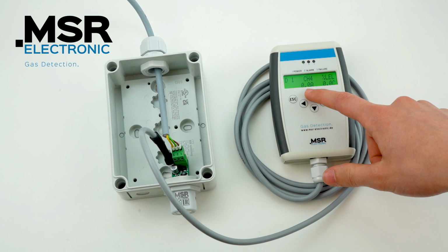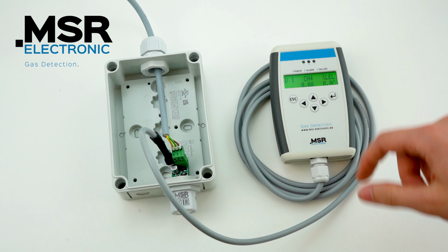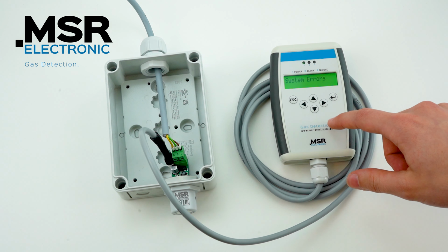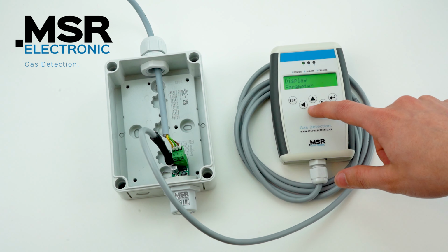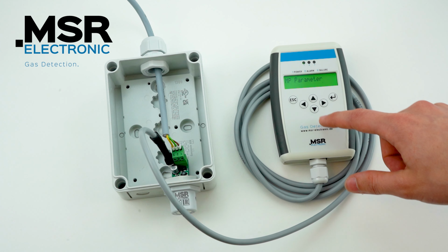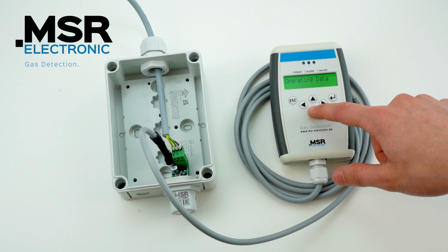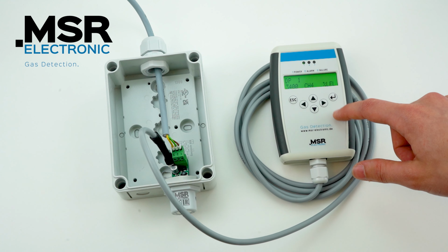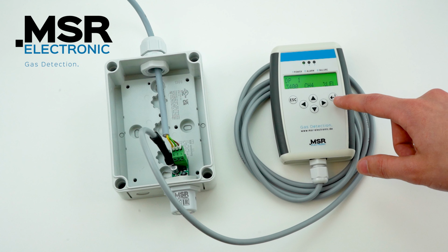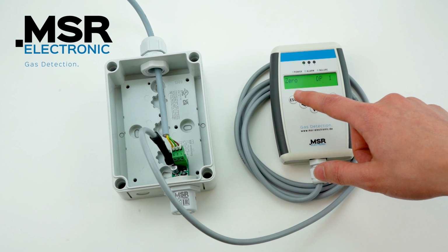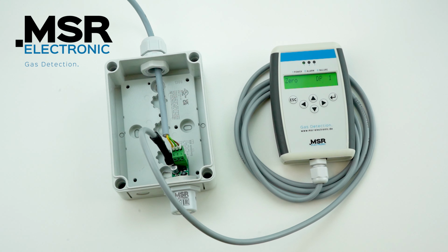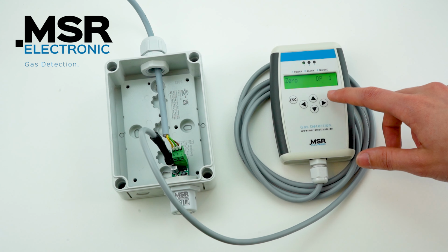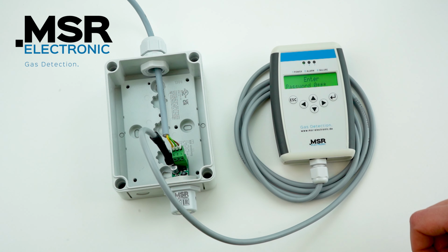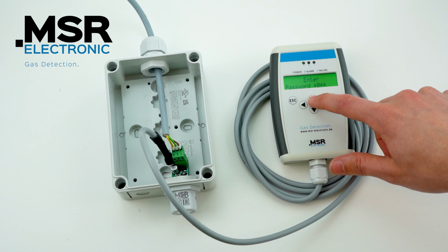Then we open the Installation and Calibration menu and then the Calibration submenu. There we select the correct sensor. For the 0-point calibration, we now start with the next step. It is important to note that for each sensor it must be individually checked whether a zero gas is required for the 0-point calibration. In our case it is a methane sensor. Since methane in the ambient air can be excluded, we do not need a zero gas.